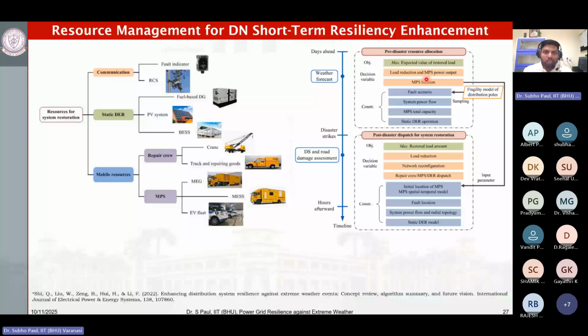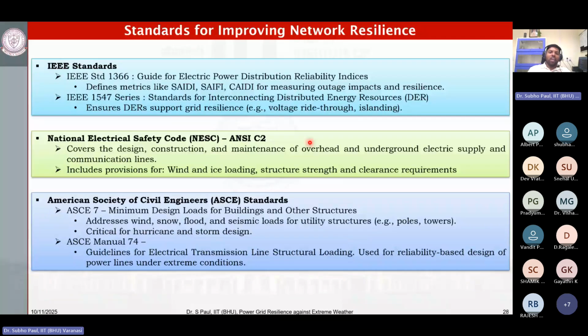Few standards are mostly followed to design your system to be more resilient. First is the IEEE standard 1366, which guides electric power distribution reliability indices, defining SAIDI, the outage duration index, and outage frequency index for measuring outage impacts and resilience of the network.